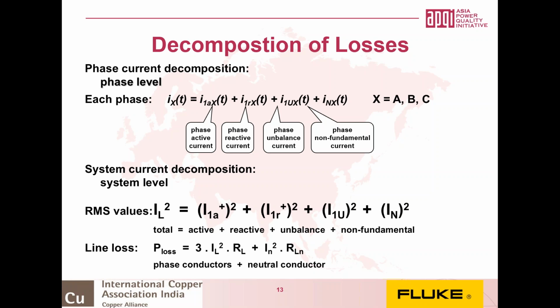So as we break those down, why do we split them into these parts? Well, this is going to give us a good indication of where to look for improvements. If we don't like the outcome of the total line loss, we can look at exactly where that line loss is coming from. To calculate the total power loss in the transmission system or local distribution system, we could add together the squares of the RMS values of the individual current components and multiply each one. That needs a lot of calculation, so we developed this shortcut. By defining the system current IL, we can quickly calculate the system level RMS values of the phase current by category: active, reactive, unbalanced, and non-fundamental.